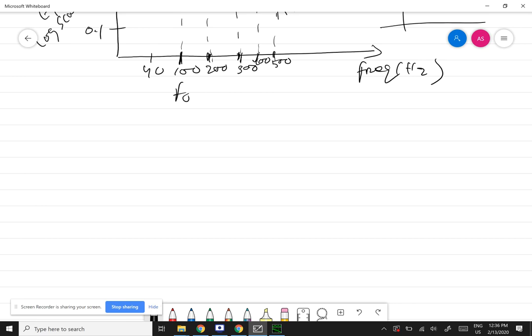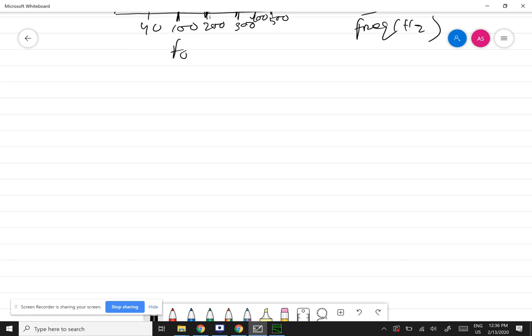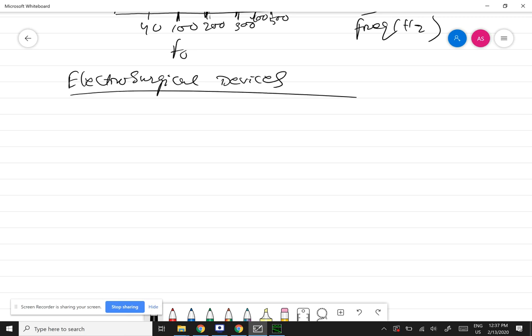Tomorrow is the last class before mid-sem. I want to do a little bit on electrosurgical devices — that will be the last topic before mid-sem. The ESU (electrosurgical unit) uses electrical power to do surgery. You can use electrical current to cut tissue, join tissue, dry up tissue, or clot blood — there are different modes to achieve that. Many laparoscopic devices have electrosurgical units attached to them.